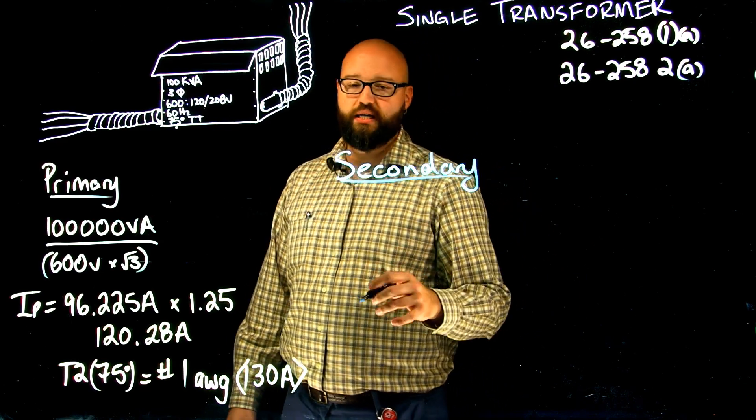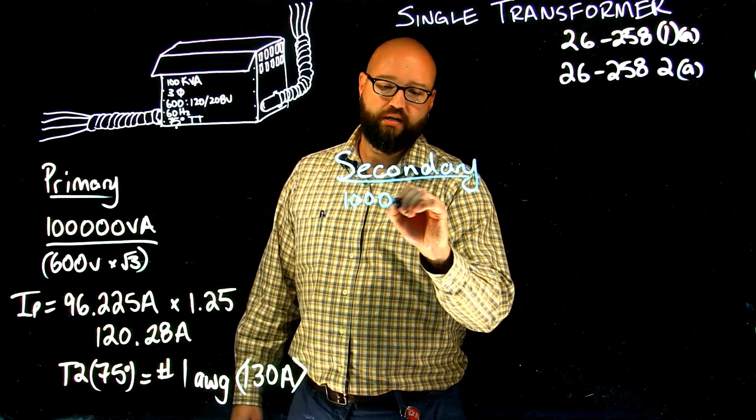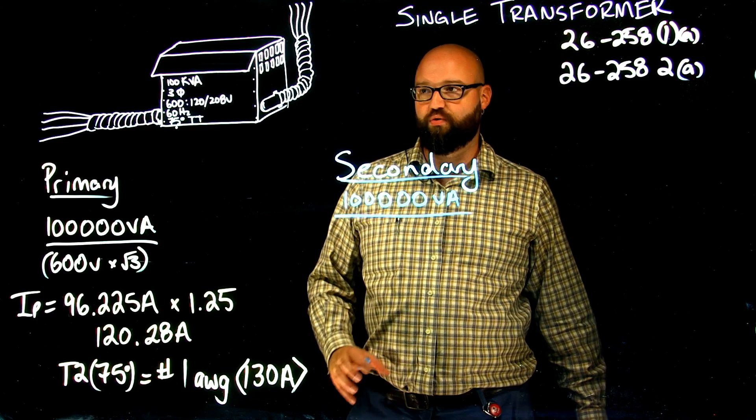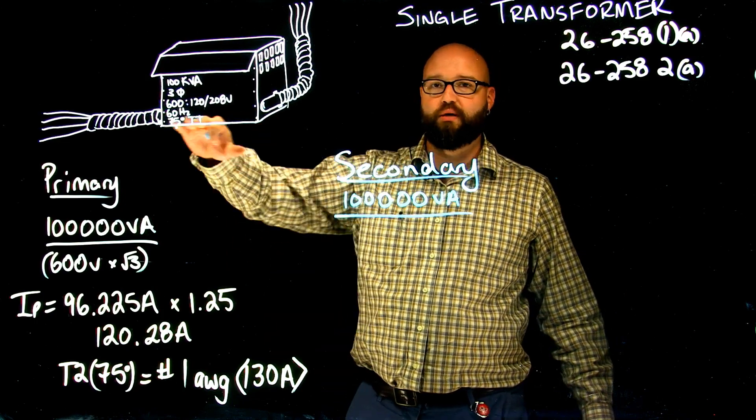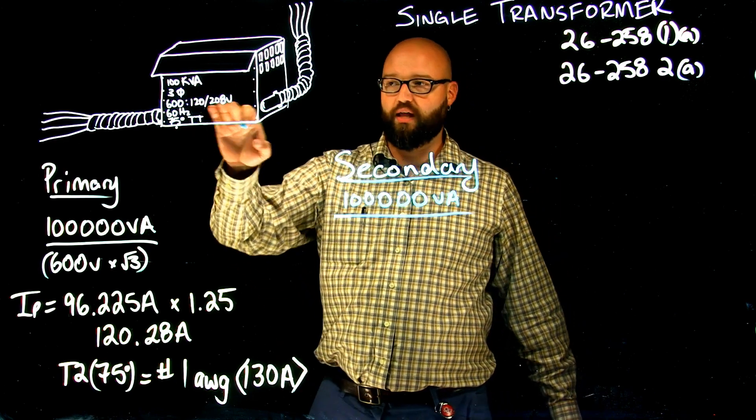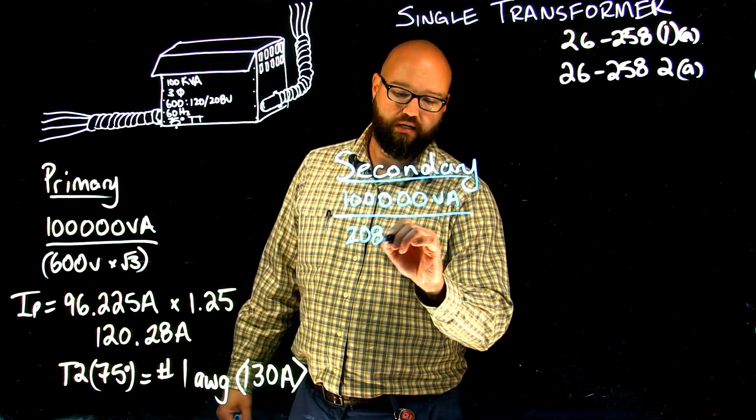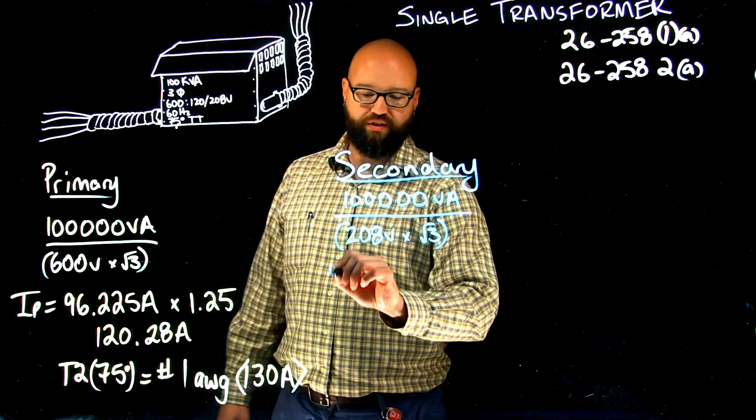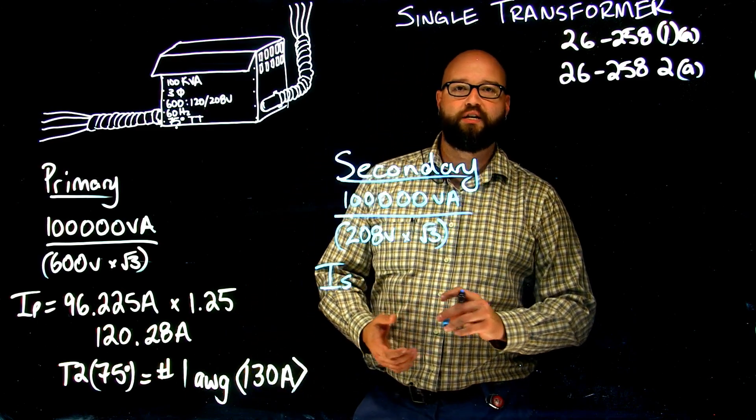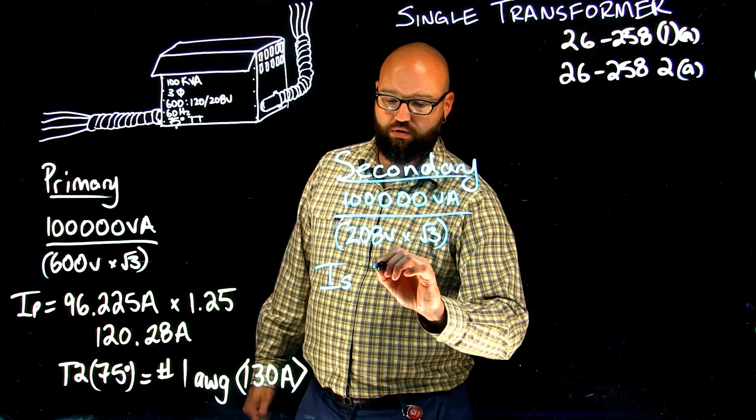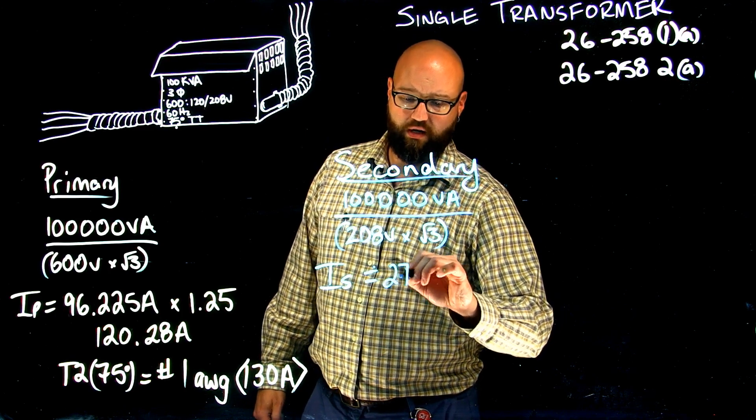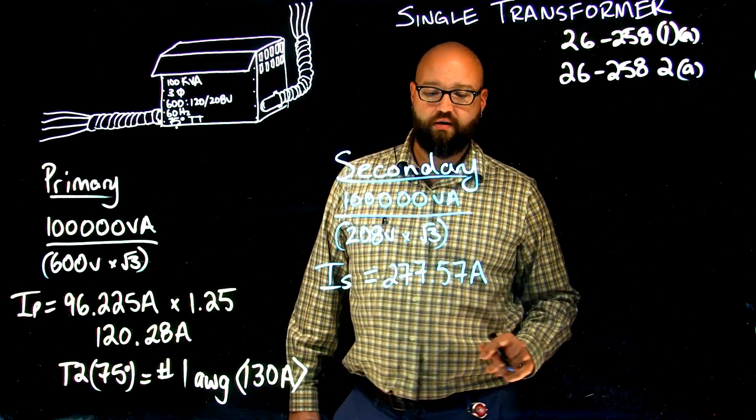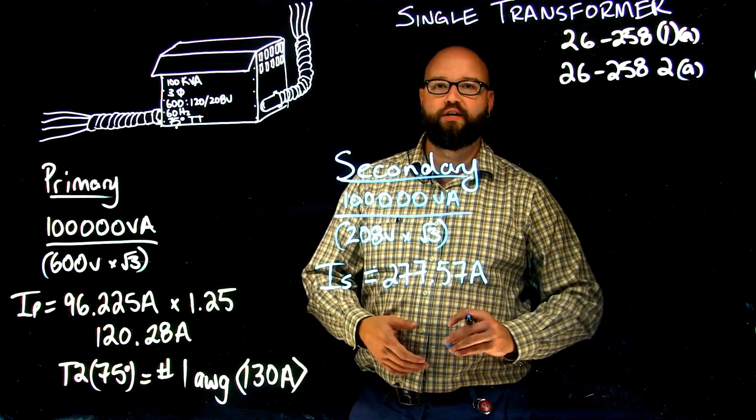Again, VA in equals VA out. 100,000 VA divided by my secondary line voltage times root 3. I have 120/208, 120 being my phase voltage, 208 being my line voltage. That's the number we're going to use, 208 volts times root 3. Make sure we get that in brackets. I end up with current on the secondary, rated current is around 277.57 amps. That is how much current will flow in the secondary at rated load.